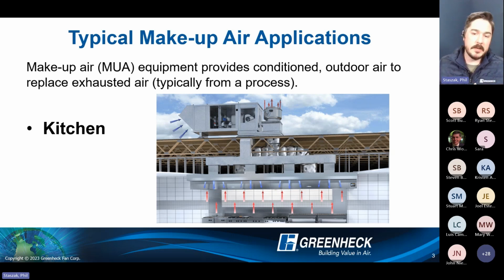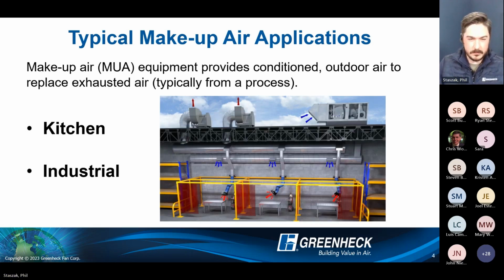You want a slight negative in some cases, a slight positive in other cases, but we're making up for whatever that process exhaust is. And since we're bringing in 100% outside air to make up for that, we're going to want to temper it in one way, shape, or form. It's not always a perfect condition outside, and in a makeup air, especially a kitchen, we're aiming for 60 degrees, which is usually plenty. It's more focused on the cooling side for a kitchen because of the heat gain in the space than anything else. But again, heating is the primary function.